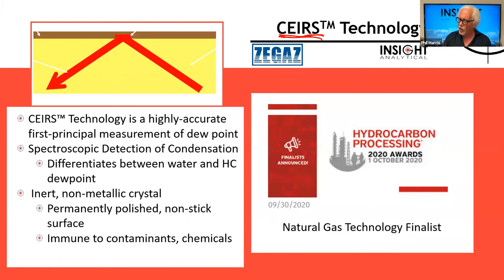CEIRS technology. Acronyms are always fun, right? The C is for chilled mirror, E is for evanescent, talking about evanescent waves, and infrared spectroscopy. So IR, chilled mirror, evanescent, infrared spectroscopy. It's a unique technique that was developed by ZEGAZ. Sohrab is on here. Sohrab is the president of ZEGAZ and was instrumental in bringing this technology to the world. It allows for a spectroscopic detection of condensation. And this is what separates it, because using the spectroscopy part, we can tell the difference between the water and the hydrocarbon dew point.